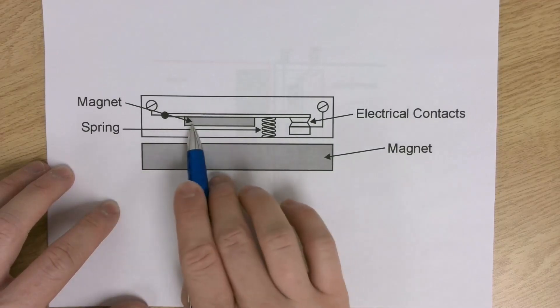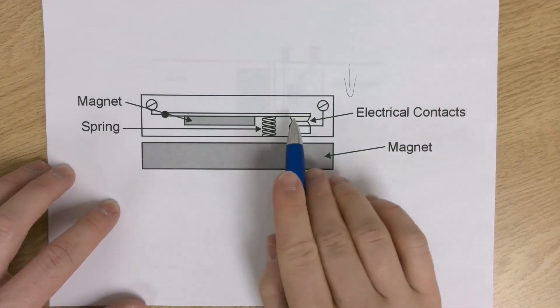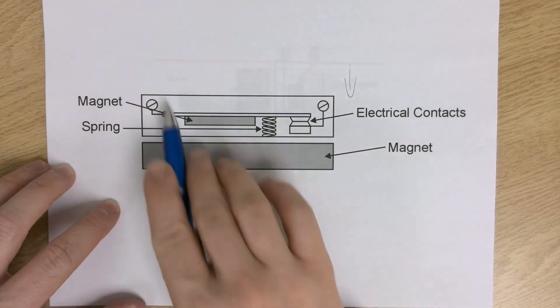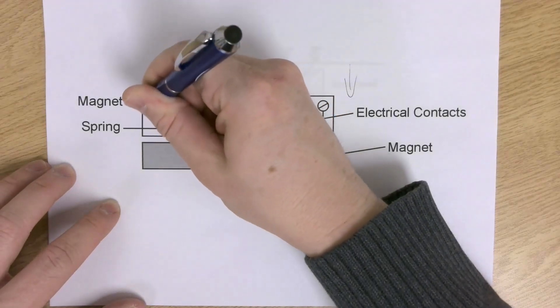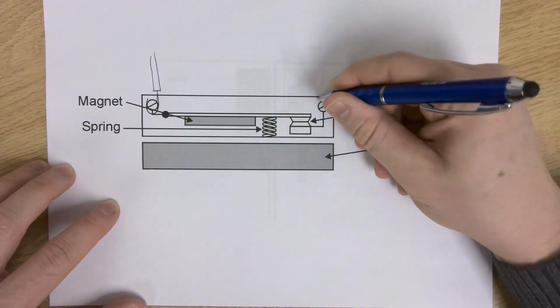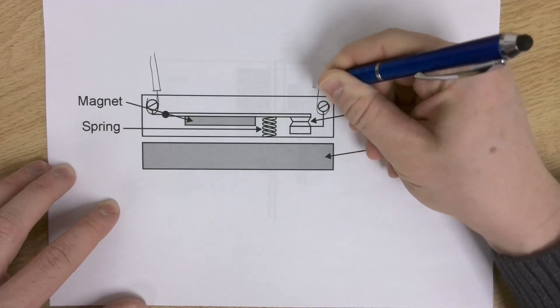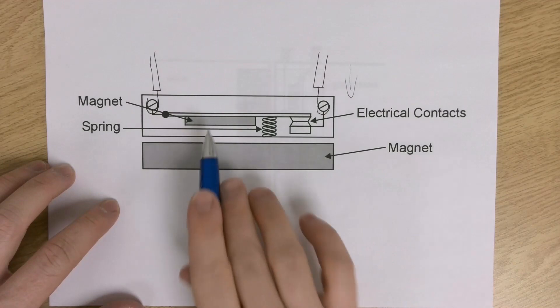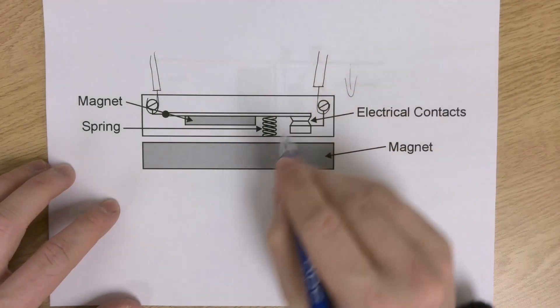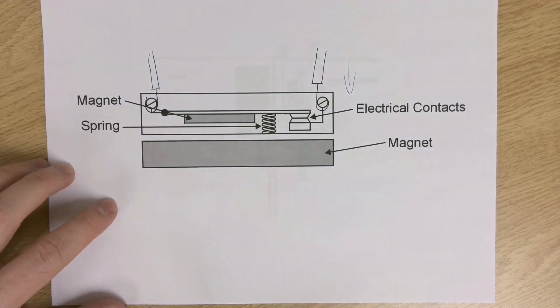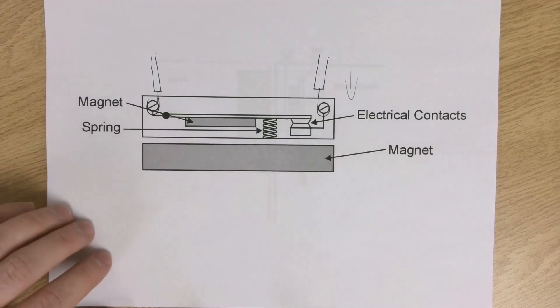This is just a magnet, and then this part of the device has a magnet that, when close to the first magnet, pulls an armature down making contact — because we terminate our wires on this screw. When this magnet gets moved away, the spring pushes the armature up and it breaks the contact. That's a basic magnetic reed switch.